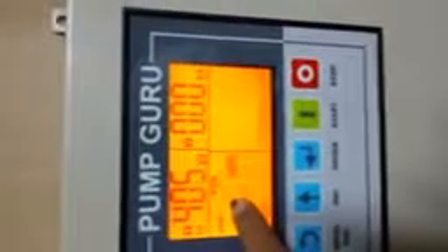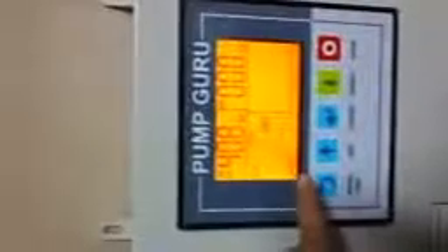So there is a setting of the pressure low and high inputs as digital inputs. So you have to have a constant pressure flow. This will give a chance to flow for 15 seconds. If it flows below 15 seconds, the pump gets off. The next setting is for the top tank and the bottom tank. Both the levels are being set, so the low and the high setting, and here also the top low and the high settings.